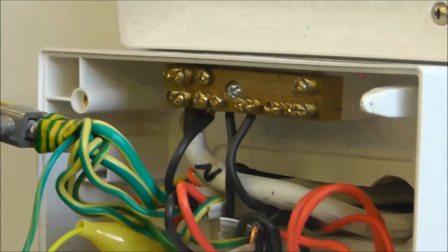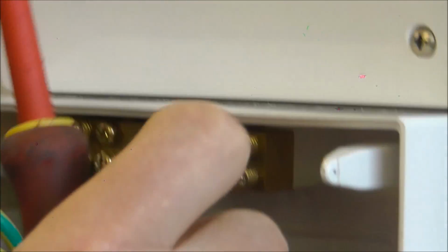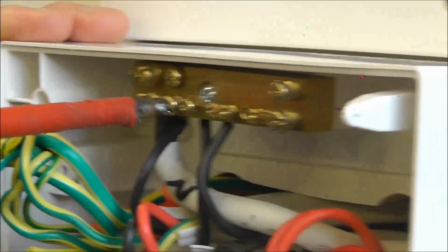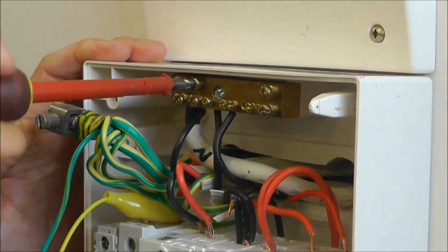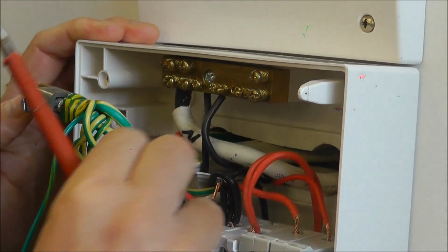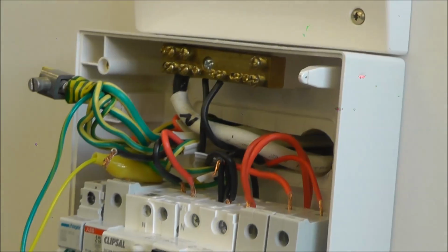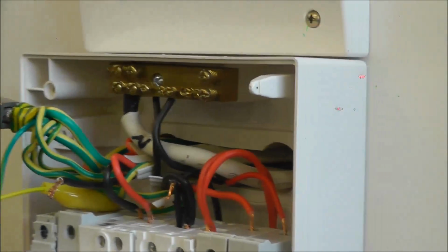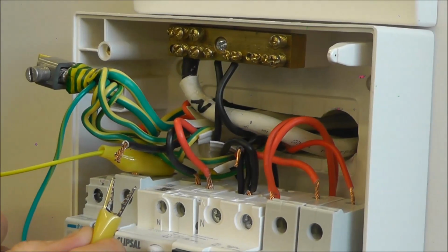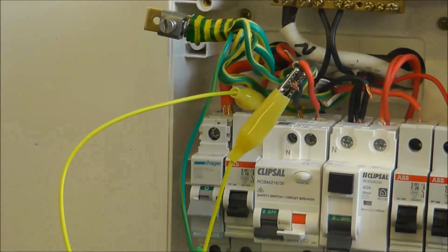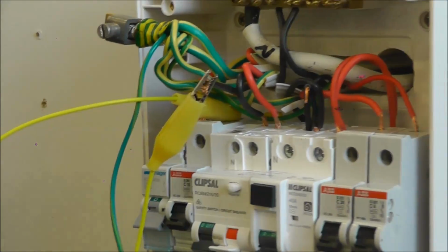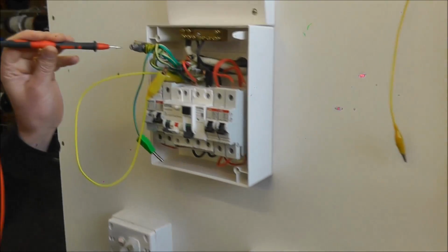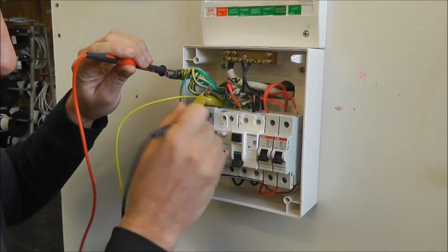I don't believe that you need screwdrivers. I think that it's easily accessible. So I need to get the neutral that belongs to that circuit there, so I can test it. So it's not in relationship to the others, as Mitch Turner very nicely pointed out, apprentice of the century. Now, I'm going to join up active and neutral here, yes? So I've joined up live parts for that final sub-circuit. 500 volts on in between earth and that.